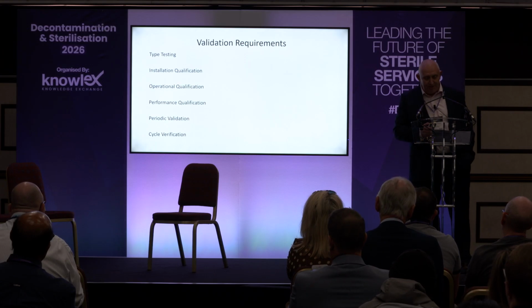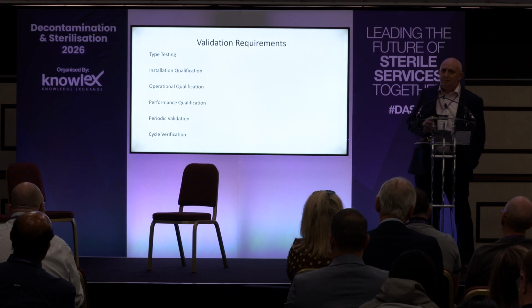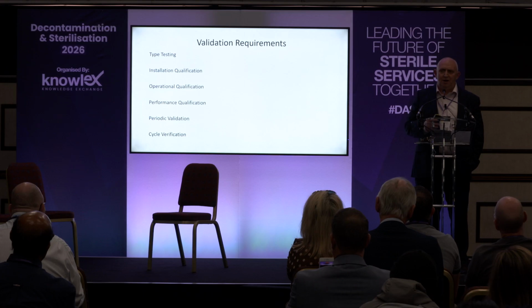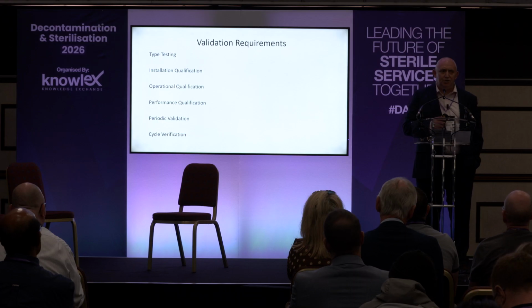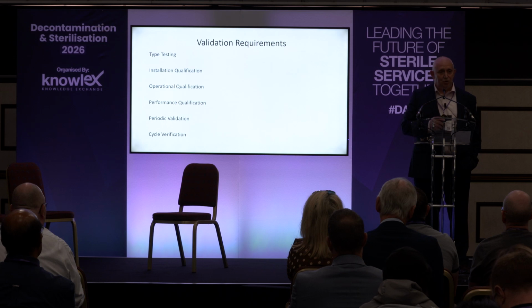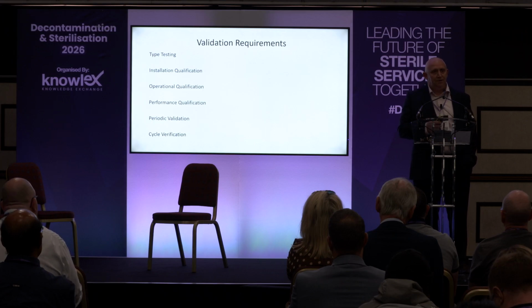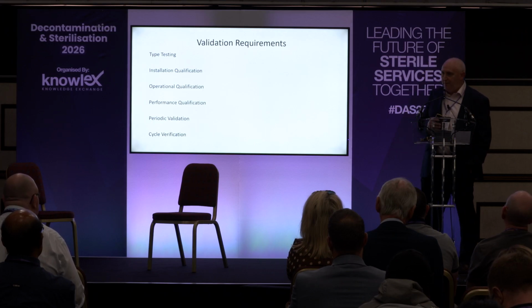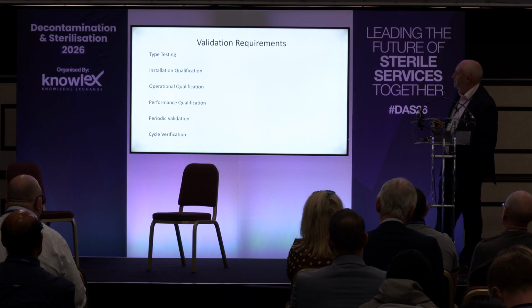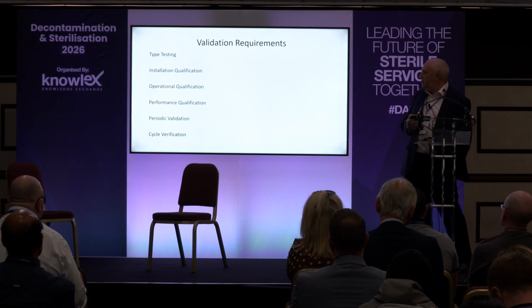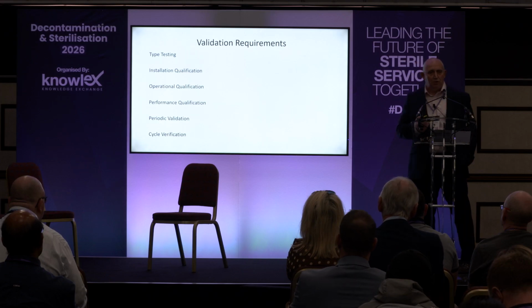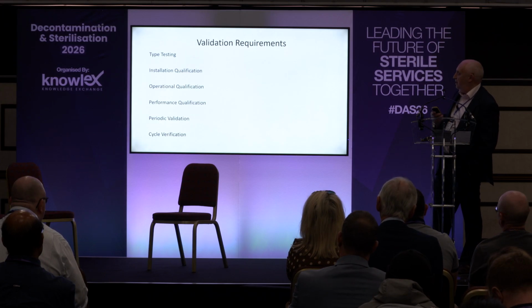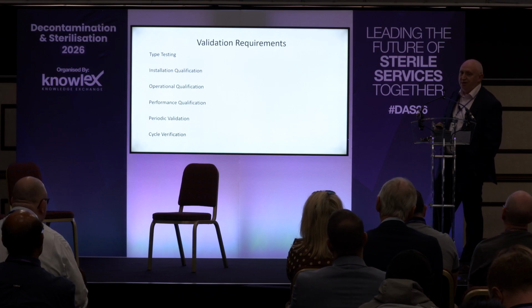So validation requirements, type testing, we highlighted earlier. But type testing is a grey area, because you ask manufacturers, can I see your type testing information? How many actually come forward with that information? Yeah? They will claim it as commercially sensitive, and I probably agree with that. However, in the event of a debate on the effectiveness of a process, you need to have that information. Then we have the standard validation requirements: installation qualification, operational qualification, and performance qualification. We have periodic validation, and we have cycle verification.